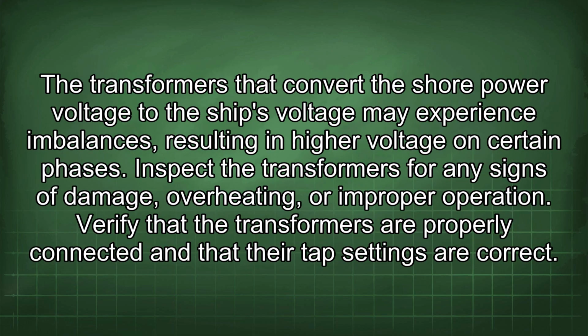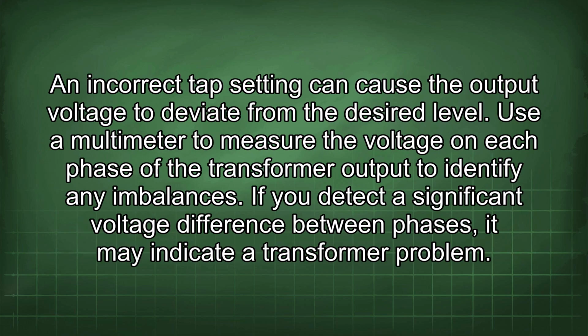The transformers that convert the shore power voltage to the ship's voltage may experience imbalances, resulting in higher voltage on certain phases. Inspect the transformers for any signs of damage, overheating, or improper operation. Verify that the transformers are properly connected and that their tap settings are correct. An incorrect tap setting can cause the output voltage to deviate from the desired level. Use a multimeter to measure the voltage on each phase of the transformer output to identify any imbalances. If you detect a significant voltage difference between phases, it may indicate a transformer problem.